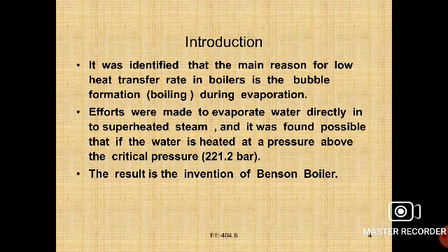You can observe here it was identified that the main reason for low heat transfer rate in boiling is the bubble formation during evaporation. Efforts were made to evaporate water directly into superheated steam, and it was found possible if the water is heated at a pressure above the critical pressure, 221.2 bar.